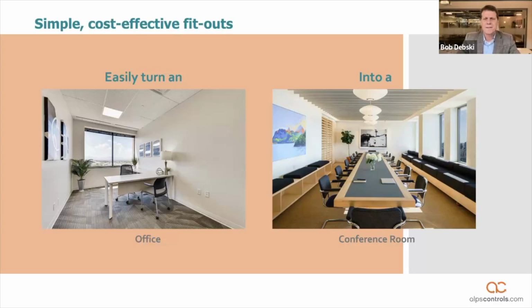So if you wanted to convert an office into a conference room, that meant not only did you have to do the demolition of the space, but you had to demo the box. You had to demo the controls. In many cases, when that demo occurred, the communication network was severed. And in addition to that, you would demo all of the branch ductwork from the box all the way out to the main. With the smart air valve, that's all eliminated. You keep the controller, you keep the box. You don't change the ductwork to the branch, and you don't have to do any demolition that can damage the network. It significantly reduces the time required for a fit out, and the cost.